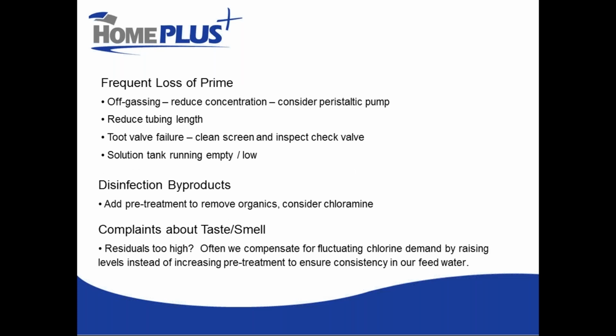Okay, this is the last slide that I have, and then I can take some questions. But just a couple of other common problems that we see on chlorination systems. One is off-gassing, which results in a loss of priming of a pump. The stronger the solution you run, the more likely it is that you will have off-gassing. So again, dilution helps reduce off-gassing. Off-gassing basically is chlorine gas or other gases, carbon dioxide and so on, coming out of solution and forming air bubbles in your injection tube between the foot valve and the pump, and between the pump and the injection point.